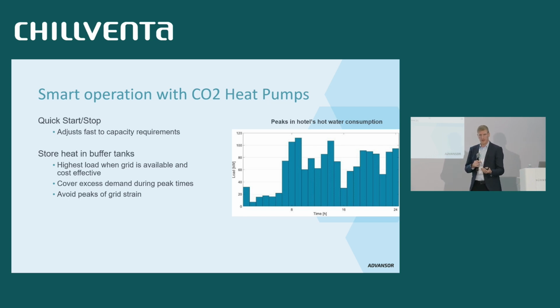If we then look at the price of electricity, that is quite often where the electricity is also cheaper. So, for example, instead of operating the heat pump according to the specific heat demand, we could more use the capacity of buffer tanks: operate the heat pump full speed during the night time, buffer up a lot of energy, and then stop the heat pump at 7 o'clock in the morning when electricity prices are high and we have high consumption of hot water. Of course, if it's an air-to-water heat pump, we will have a slightly lower COP operating at lower ambient temperatures during night. But if the electricity prices are 1/3 of what it is during the daytime, then it makes sense to do so. So smart operation is really something that we need to look into to get the overall best efficiency of the system.